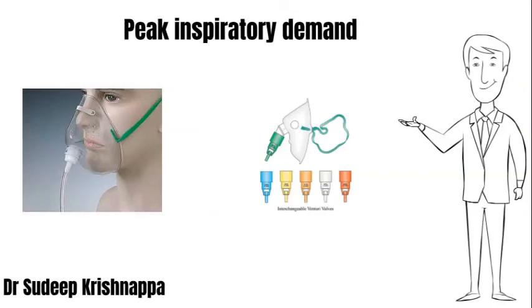A Venturi mask generates a total flow that is generally far in excess of peak inspiratory demand across a wide range of tidal volumes, respiratory rates, and I:E ratios. There is no further need for additional room air to be entrained, as the entire inspiratory demand is met by the flow generated by the Venturi device. As a result, the FiO2 remains constant.